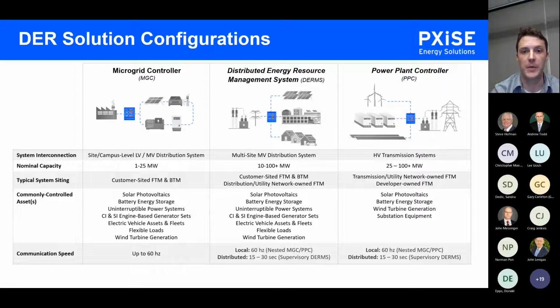What we find most interesting, and something that Lee and Patrick will dive into, is how these two different control strategies, the microgrid controller and the power plant controller, really interplay with one another when they're interconnected into the same distribution level circuit. So having a means to issue commands to both microgrid controllers at customer sites and power plant controllers at utility scale development, and making sure that distribution or transmission circuit they're interconnected to is operating in a stable and efficient manner.